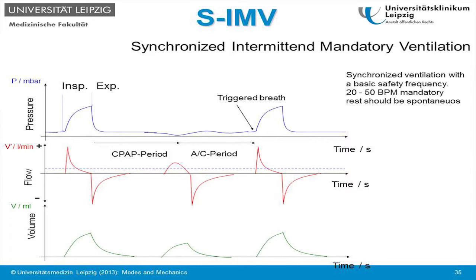You can also, with a triggering device, like any of the sensors I mentioned, do synchronized intermittent mandatory ventilation, SIMV, which is basically the same as IMV in terms of support. The patient gets some of his breaths supported by the machine, but not all. The patient initiates a breath here in the middle, which is not supported. But the machine has time windows to place the machine breath in synchrony with the patient's efforts. So these breaths are applied at times when the patient tries to inhale anyway, but this is not happening on every breath of the patient. We have to use a lower machine frequency to give time for the interaction to work out.